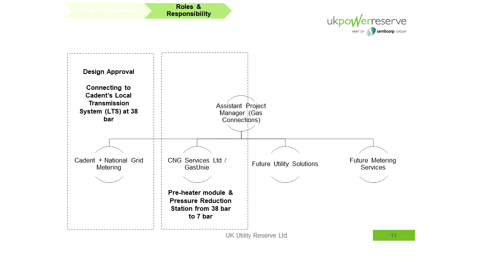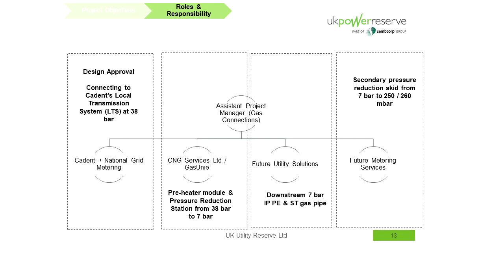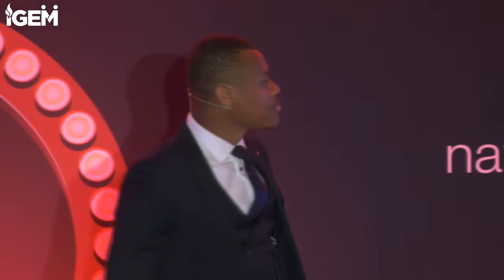With CNG Services, basically managing the delivery of the pressure reduction station and dropping that pressure to about 7 bar. With Future Utility Solutions, the delivery of the downstream pipe works. And with Future Metering Services, dropping the pressure from 7 bar to 250 to 260 millibar, which is used at the reciprocating engines.